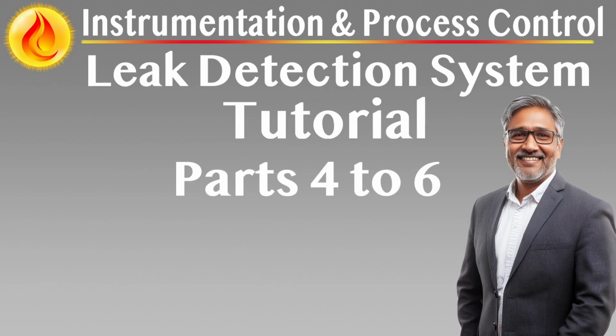While highly effective for sudden and large volume leaks, negative pressure wave detection is less sensitive to slow developing or pinhole leaks, which may not generate sufficient pressure disturbance to trigger a detectable wave. To improve signal clarity and reduce false positives, dual transducer systems are often employed. These systems use two pressure sensors placed at a known distance apart to differentiate between legitimate leak signals and ambient noise.